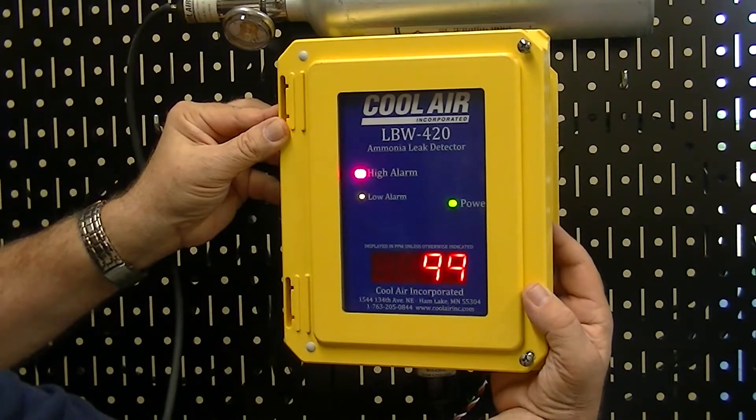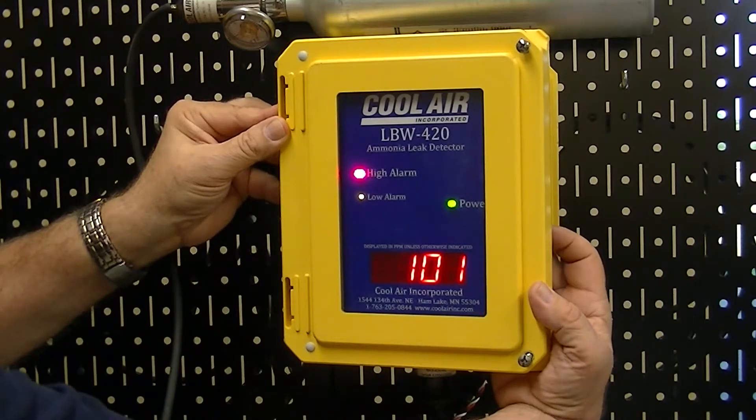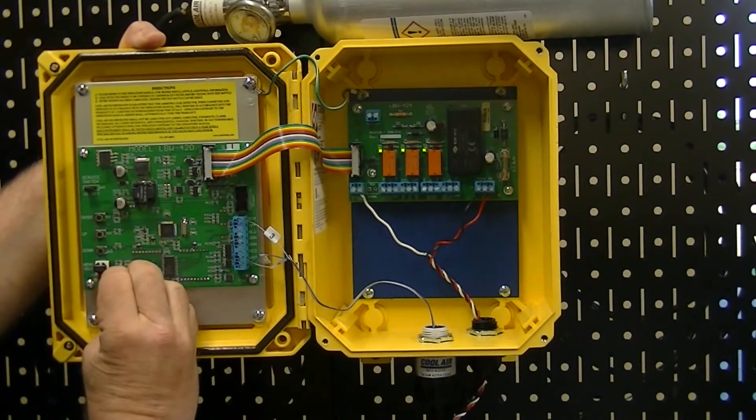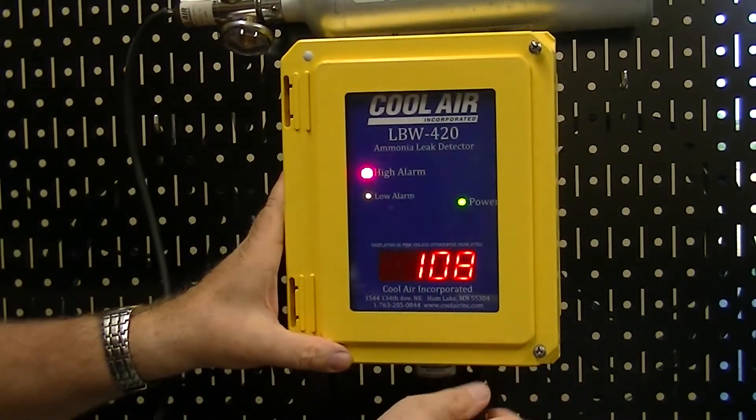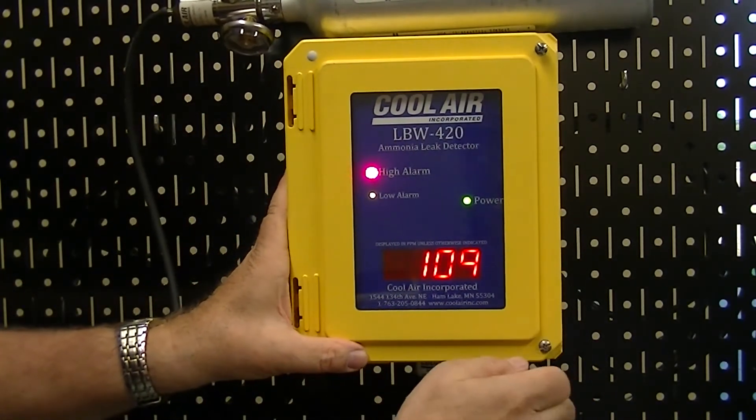At your two minute mark you want to hit your enter button for two seconds. Turn your switch position back to zero, remove the set one jumper and remove the gas.